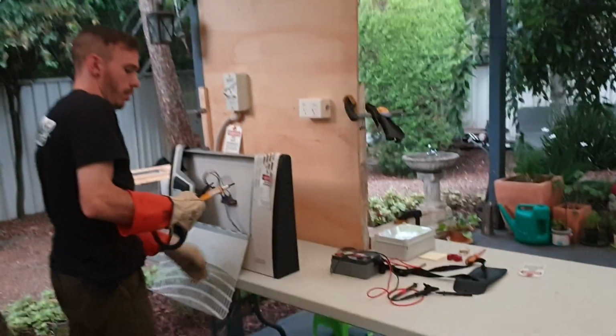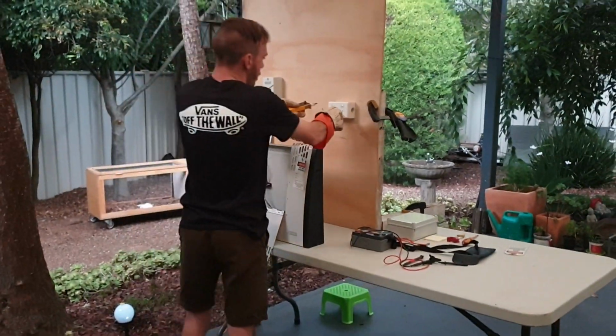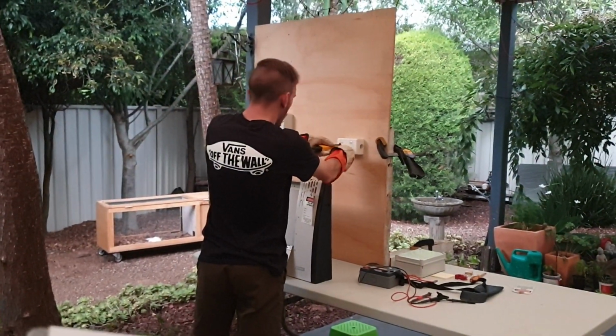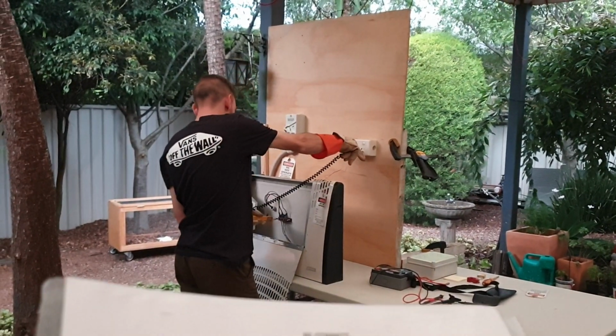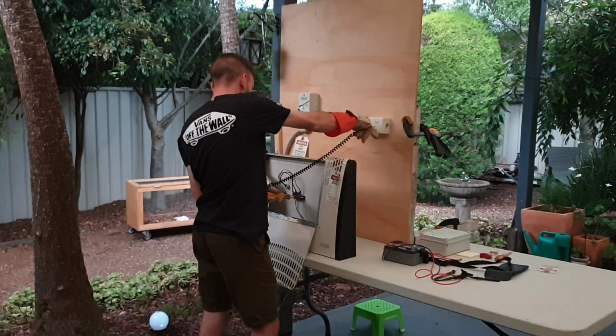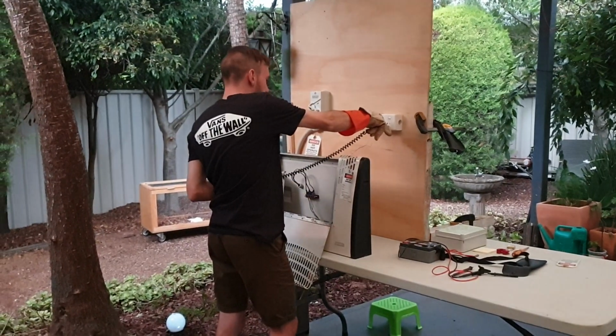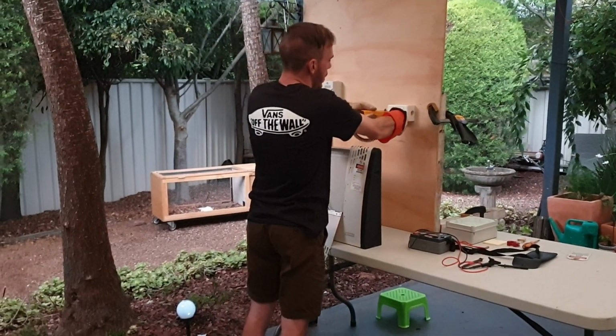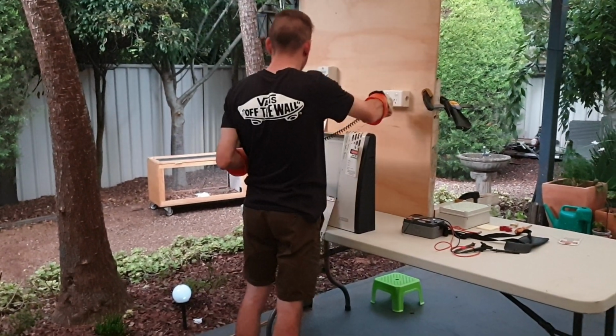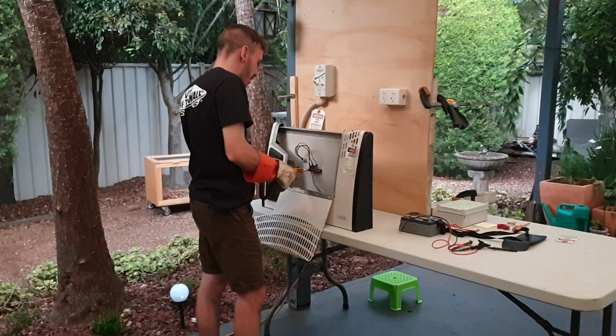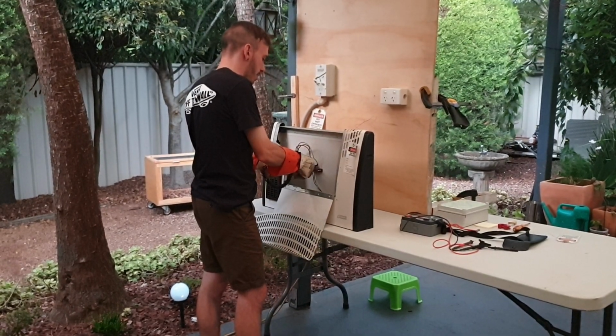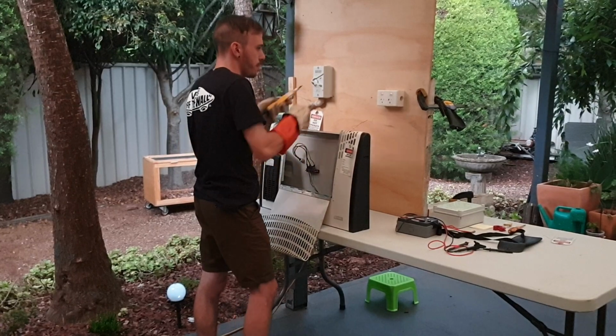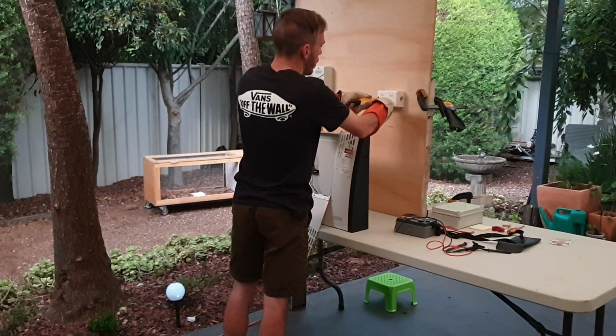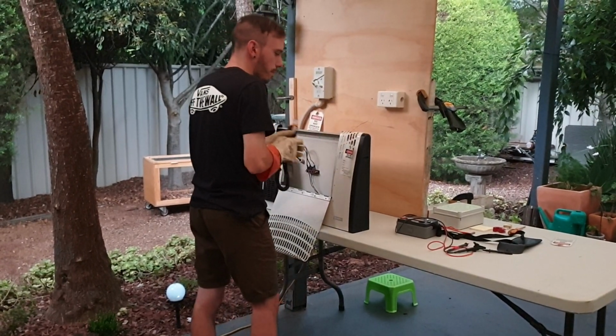We can now turn the power on. Test the voltmeter again. Get a voltage. Test from the known earth to the active, neutral and earth. Only the active has voltage, which is correct. We're going to retest the meter. This has voltage. Now we're going to test between the three conductors: active to neutral, we have voltage; active to earth, voltage; neutral to earth, no voltage, which is correct.